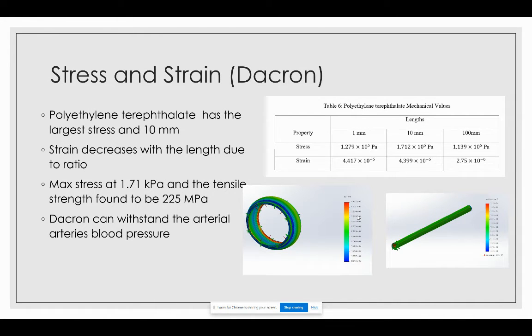For Dacron, the largest stress again occurs at 10 millimeters and strain decreases with length. The maximum stress was 1.71 kilopascals, and the tensile strength was found to be 225 megapascals. Dacron will easily be able to withstand the radial artery's blood pressure.